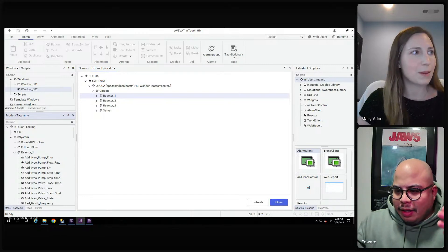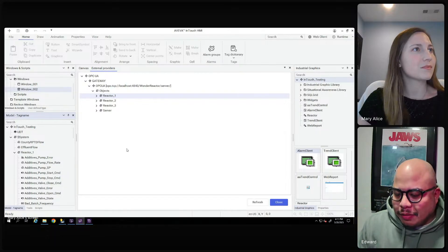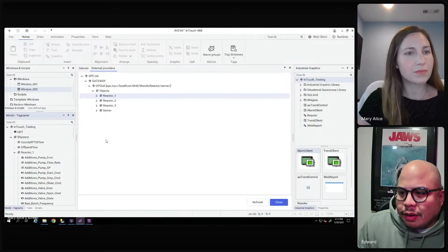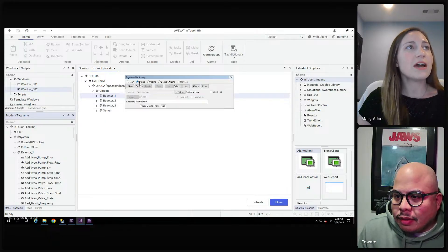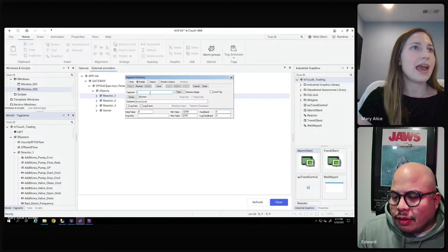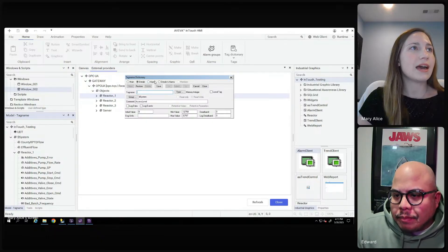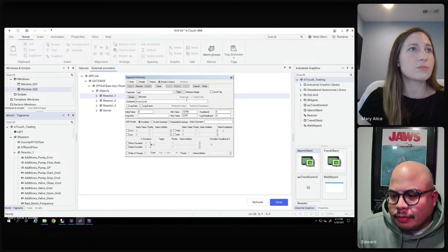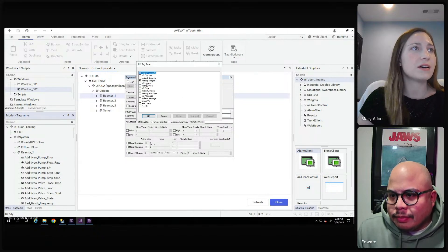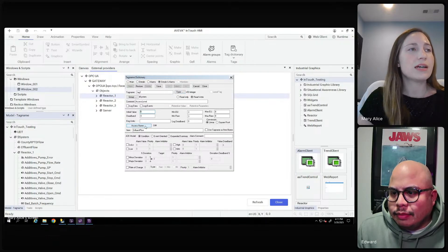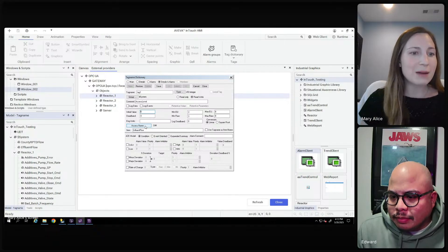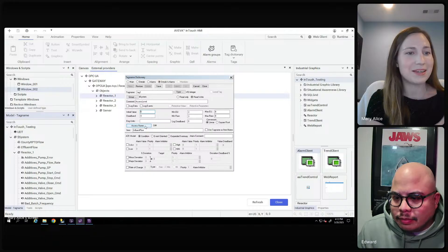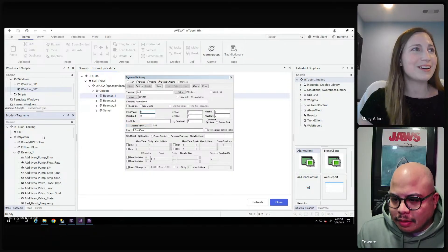Let me step back and show the general workflow with the Tag Name Dictionary, to give viewers a contrast between our newer feature set and what we used to do. In the Tag Name Dictionary, to add a tag you select New Tag, give it a name like 'Tag One', look at the different details and alarms to configure, select the tag type — for example, an IO Integer — and then specify the asset name. A lot of steps and configuration go into just one tag, whereas what I just showed you adds 70 tags in seconds.